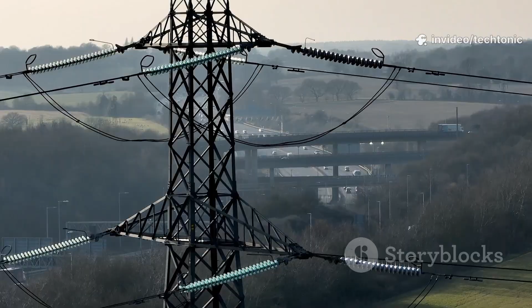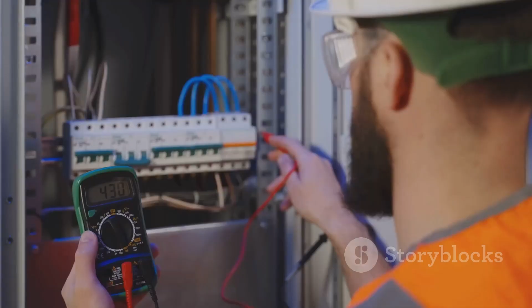In remote areas, running two wires for power is costly, so engineers use single-wire earth return, or SWER. SWER uses one wire to deliver electricity, while the Earth itself completes the circuit. At both ends, grounding rods connect the system to the soil, letting current flow through the planet. This design cuts costs and brings power to far-flung places. It's used in Australia, Africa, and the American West. The Earth's resistance is a trade-off for affordability.